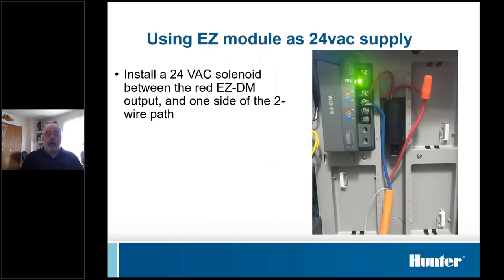EZ decoder, same thing. Only on the EZ, because it's a 24-volt system, we still may need to use the clamp-on if we've got shorts out in the field, but we can just use that module with a solenoid in line instead of having to bring in a separate transformer.